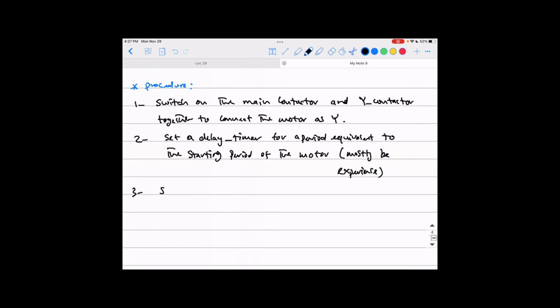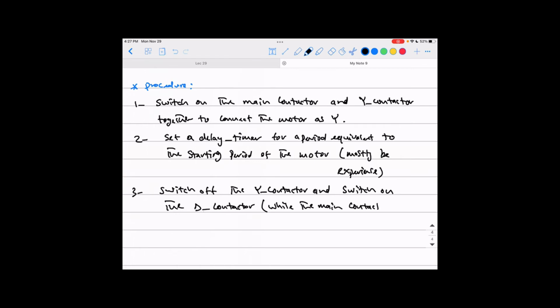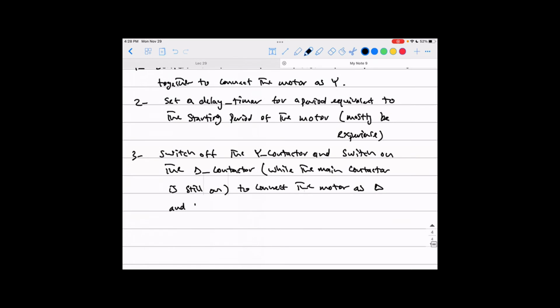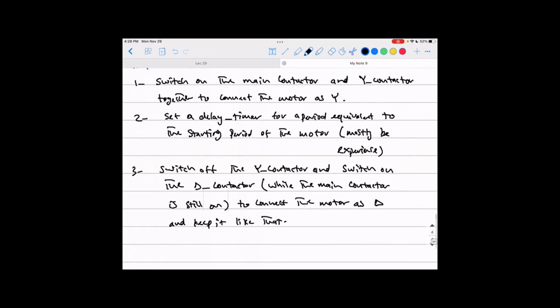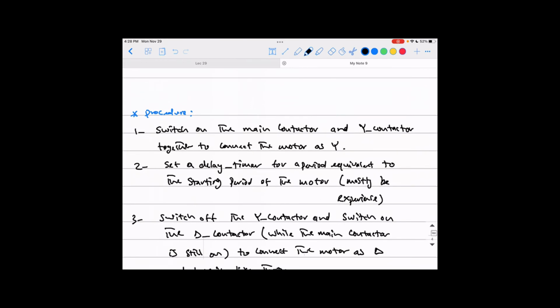And after this passes, you switch off the Y contactor and switch on the delta contactor, while the main contactor is still on, to connect the motor as delta and keep it like that. So that means the regular connection of the motor is the delta. So the motor will be connected like delta regularly and all the time. But just at starting, we will be connecting it as Y.